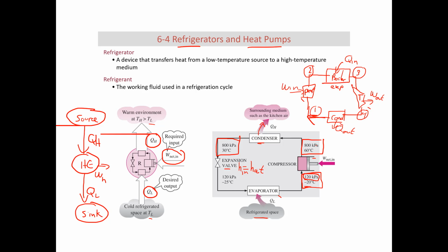Why is that a big deal? Because it drops the pressure significantly, in this case from 800 down to 120, and the temperature also drops, and it comes out as a saturated liquid vapor mixture at a very low temperature, ready to go into the evaporator and absorb heat.